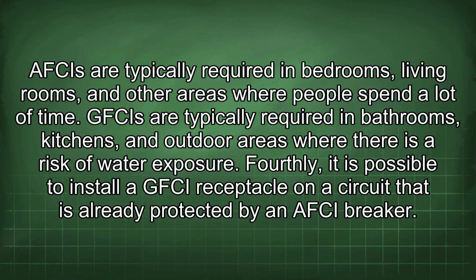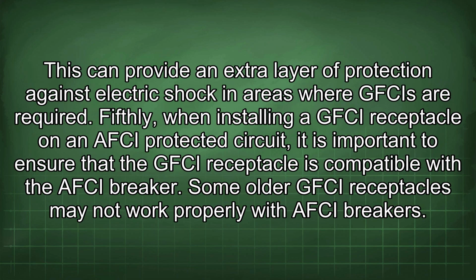Fourthly, it is possible to install a GFCI receptacle on a circuit that is already protected by an AFCI breaker. This can provide an extra layer of protection against electric shock in areas where GFCIs are required.